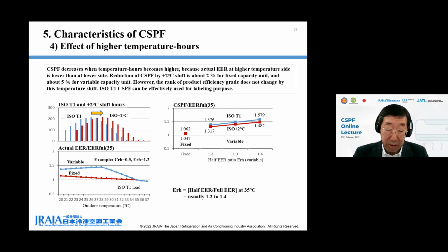This page shows effect of higher temperature hours on CSPF. The upper left figure shows ISO T1 bin hours and plus 2 degrees hours shifted to higher temperature side at each outdoor temperature TJ. The lower left figure shows actual EER divided by 35 degrees C full EER at each TJ for fixed capacity and variable capacity unit. These are same for both hours. Half capacity ratio CRH and half EER ratio ERH of the example variable capacity unit are 0.5 and 1.2.